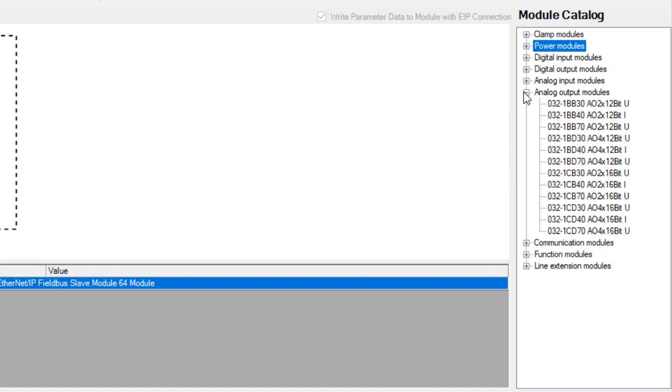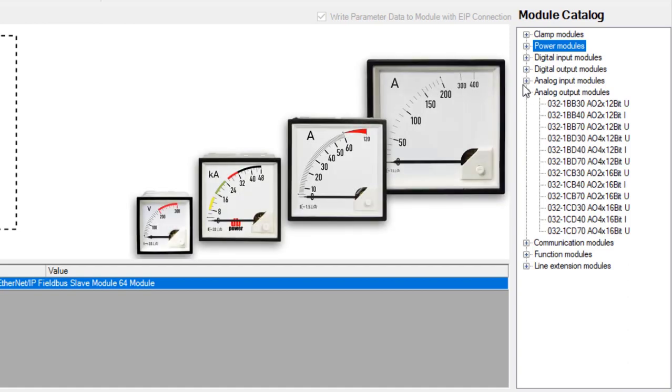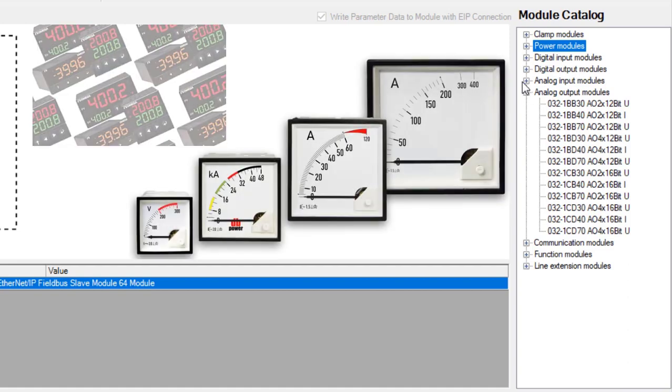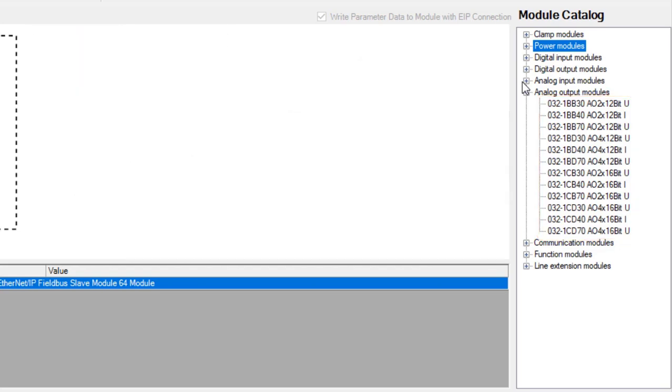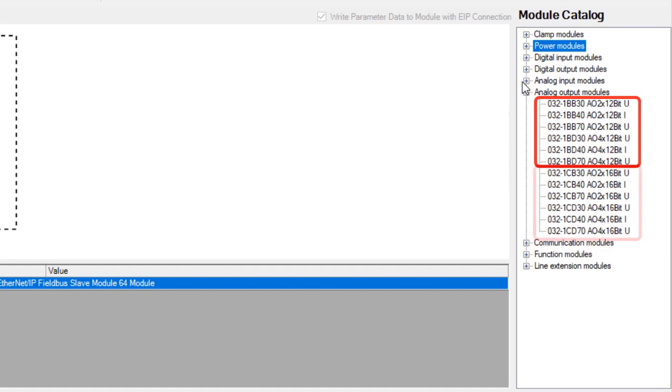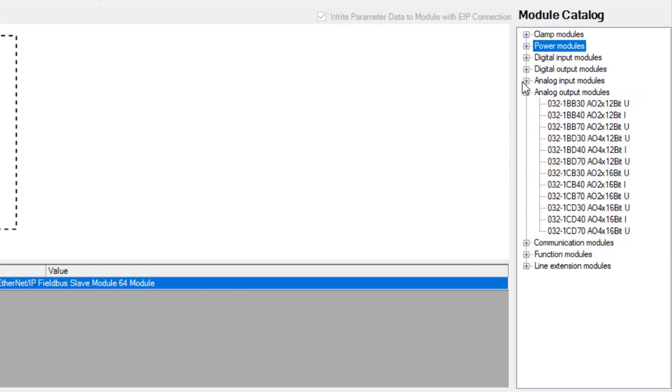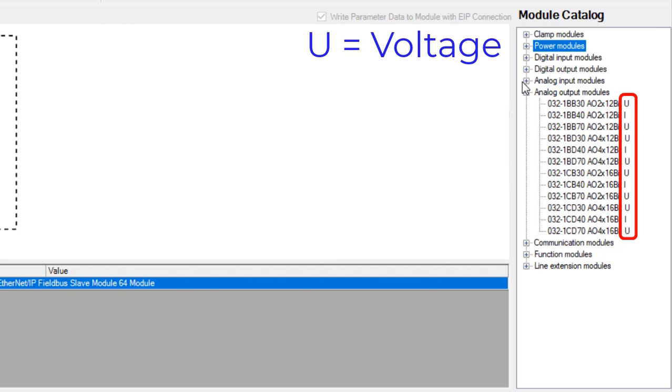Other analog devices such as analog meters and gauges, along with PID controller devices, can be used with analog output slices. These slices offer 2 to 4 outputs with either 12-bit or 16-bit output sampling resolution. These output slices can provide a voltage or current signal to the external device.